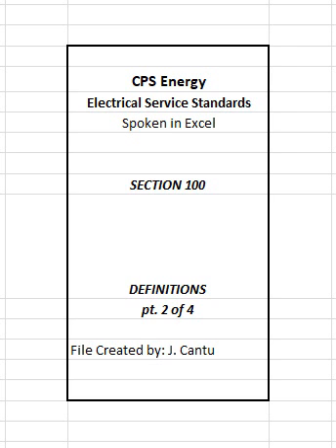Kilovolt amperes, kVA. A term used for rating electrical devices. A device's kVA rating is equal to its rated output in amperes multiplied by its rated operating voltage. Kilovolt amperes is the vector sum of the active power, kW, and the reactive power, kVAR, flowing in a circuit.